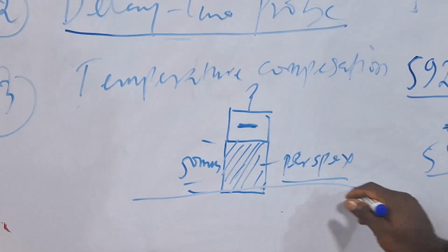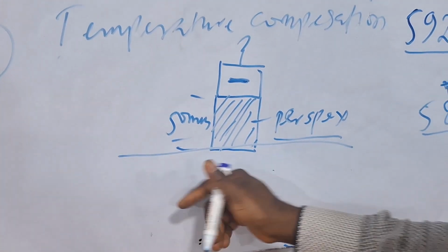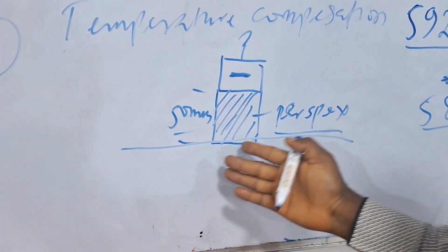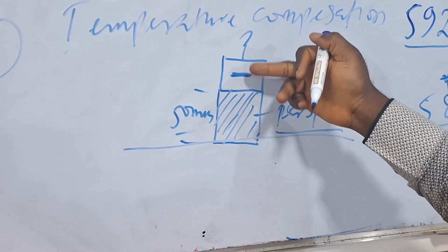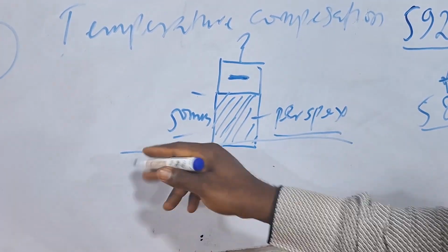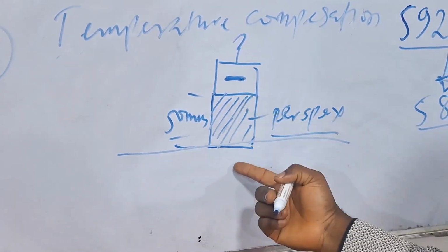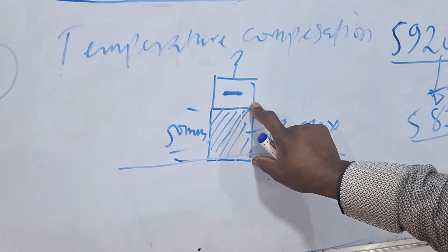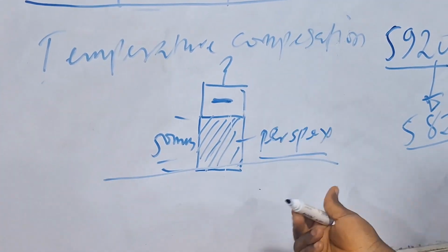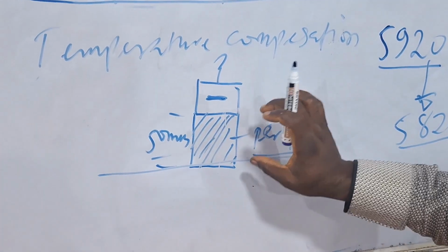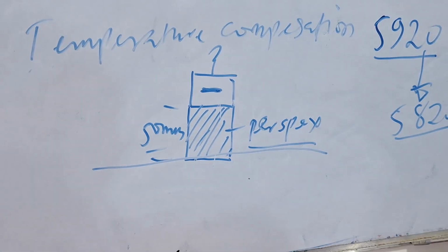So when you put it on the material, whatever changes that are supposed to affect this probe from the hot surface is compensated because of the thickness of this delay line probe. And when you are doing your calibration, you have to compensate for this change in the delay line.